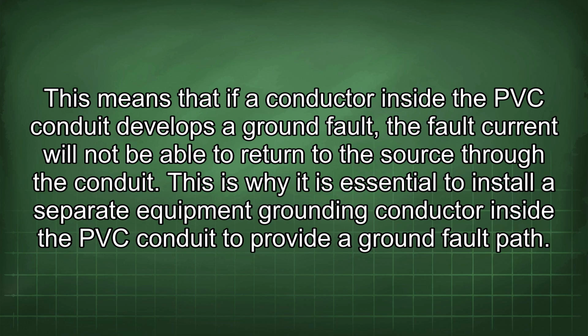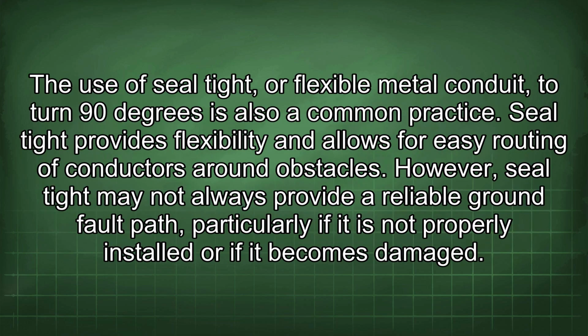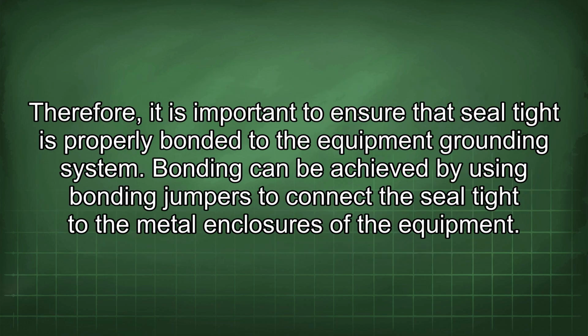This is why it is essential to install a separate equipment grounding conductor inside the PVC conduit to provide a ground fault path. The use of seal-tight, or flexible metal conduit, to turn 90 degrees is also a common practice. Seal-tight provides flexibility and allows for easy routing of conductors around obstacles. However, seal-tight may not always provide a reliable ground fault path, particularly if it is not properly installed or if it becomes damaged. Therefore, it is important to ensure that seal-tight is properly bonded to the equipment grounding system. Bonding can be achieved by using bonding jumpers to connect the seal-tight to the metal enclosures of the equipment.